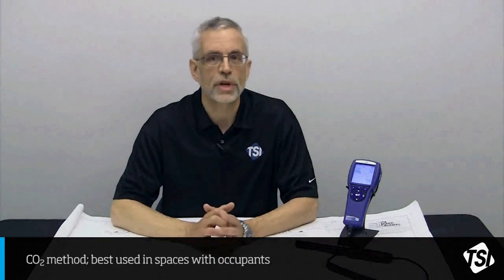For example, using temperature measurements to determine the percent of outside air is not an ideal method in mild climates where the inside and outside temperatures are too similar to each other, whereas CO2 measurements should not be used if there are not enough occupants in the space being tested to generate sufficient CO2 levels. In this demonstration, we will be showing the more popular of these 2 methods, CO2 measurements.